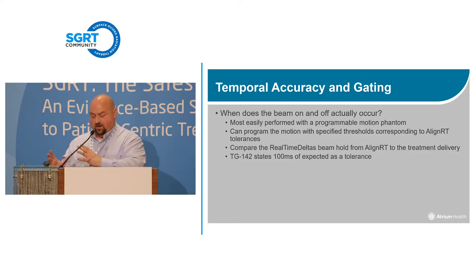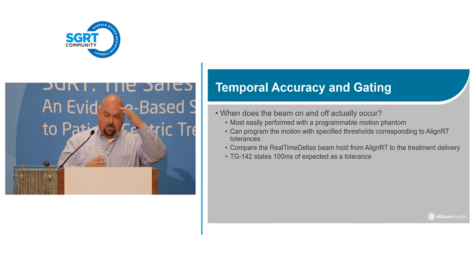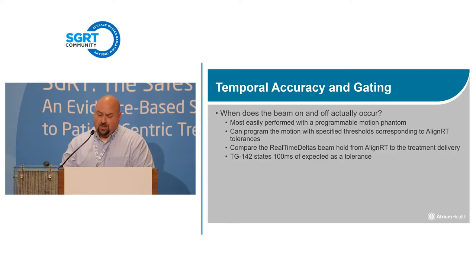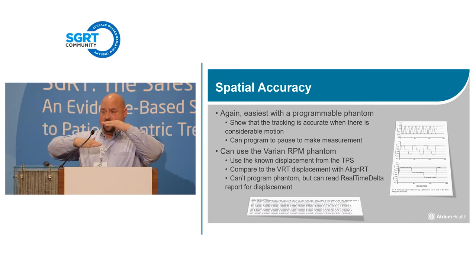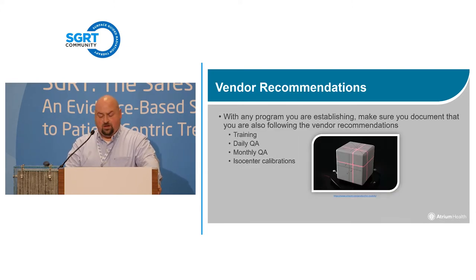We're not going to use a stopwatch — we take a phantom, deliver a plan, and look at the results. There's good data coming out of the VisionRT system in a text file you can import into Excel. Log files from TrueBeam and IX machines are also available. Try to replicate the clinical situation. Spatial accuracy matters too — if something is moving, you want to confirm that when it hits the threshold the beam actually holds, and that the system can reliably track that motion.